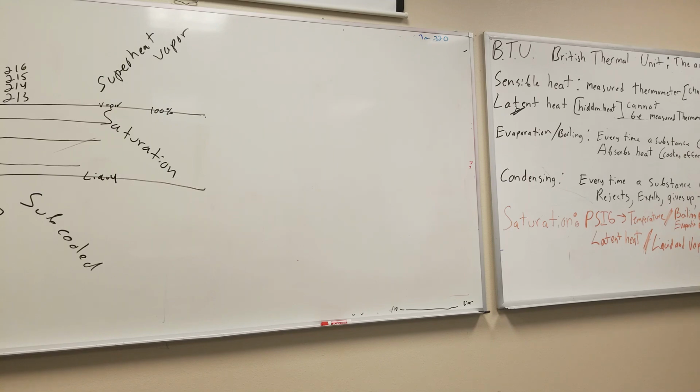And if we had, at 0 psi at this pressure, water vapor at 300 degrees Fahrenheit, it would be a superheated vapor. So 300 minus the saturation point of 212 is what? 88 degrees. Superheated 88 degrees. Steam.